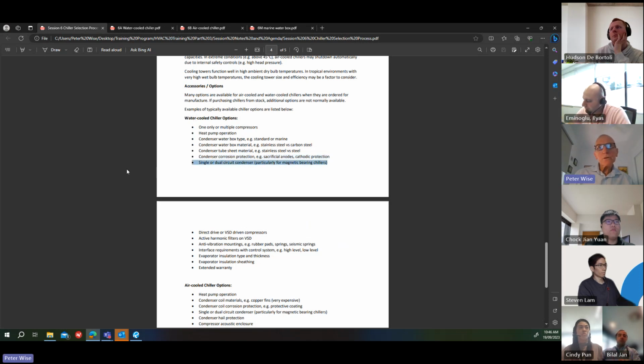You can get single or dual circuited condensers, particularly with magnetic bearing chillers. Now, this is something to watch out for. If you're looking at magnetic bearing chillers, they can get very high efficiencies, particularly in part load. So it's interesting to compare operating performances at different loadings for these chillers. They'll give you very good efficiency at, say, 50% capacity. So you might be better to run 2 chillers at 50% than run one larger chiller at 100%. You'll get better efficiency. So all these things can be looked at.